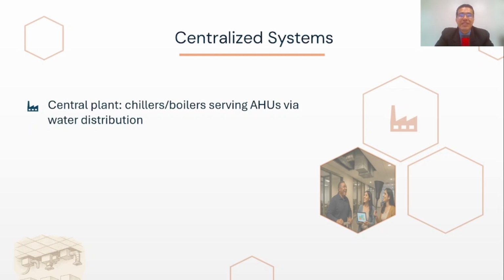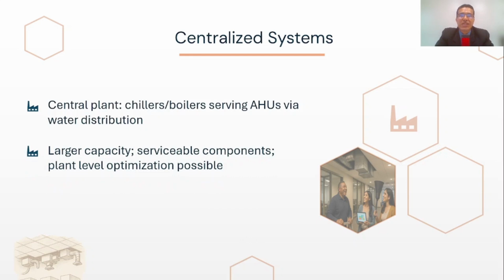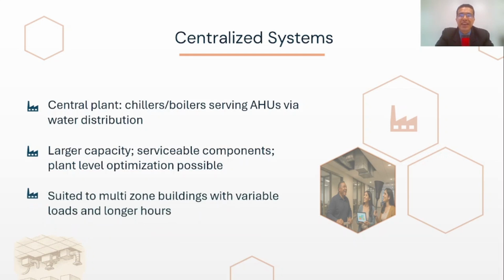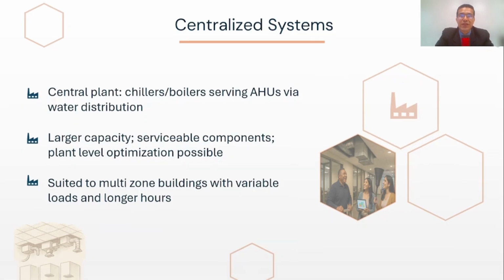In centralized designs, air handling units and heat generation are separated: air handling units serve zones while chillers and boilers deliver chilled and hot water to coils. Centralization enables coordinated control, maintenance access, and opportunities for plant-level efficiency improvements. This often aligns with buildings that have many zones and significant diversity across operating hours.